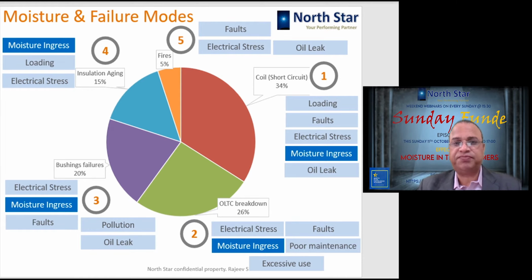So let us look at the highest failure modes in a transformer. So you see here the coils are 34%, the transformer failed because of winding. It is coil, 34%, OLTC 26%, second number, third number bushing, and fourth number insulation aging, and last is fires. So in all the five failure modes, except the fire, you can see the moisture is playing a role. Okay, so fire case is only 5%. So 95% of the transformer failures, we can say, are happening because of the effect of the moisture.